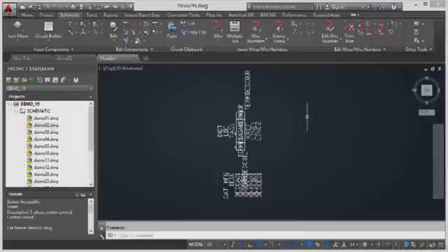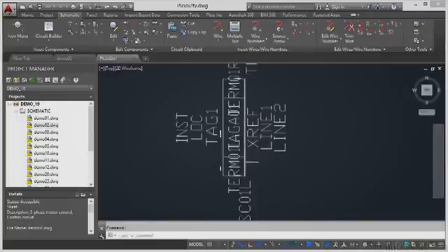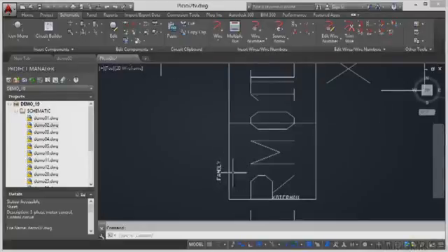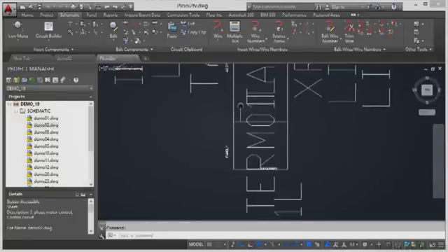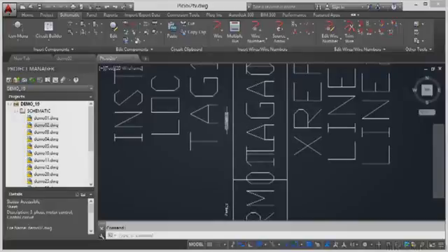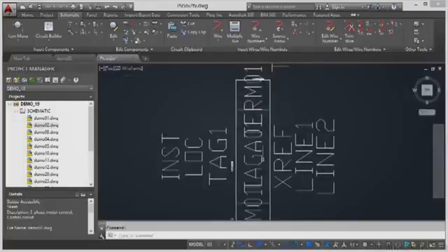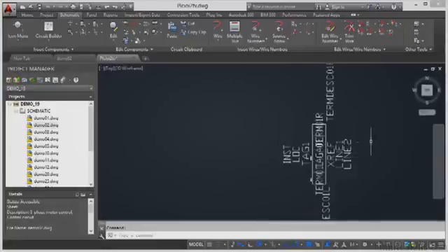And you'll notice there's not actually that much CAD information. It's all attribute driven because it links to the database. If I zoom in real close, you can see that there's the lines that make up that particular strip. But if I zoom in even closer, I've got things like family. And these little attributes here, now these are the attributes that you must not remove. They're the ones that are very important. So you've got assembly code as well. So these are the ones that you must not remove on your AutoCAD drawing for this particular symbol.